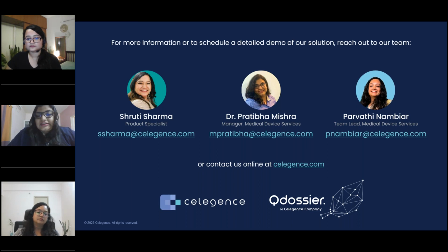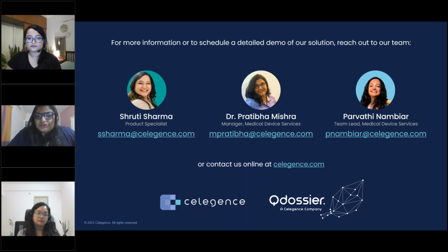In some cases, in case of devices where you don't have necessary data from literature, you can also look into PMS, which basically links to the risk documentation. So what kind of issues or complaints, or adverse events have been reported, and what is the reportable event rate, for example, for similar devices on the vigilance databases, and that can help you define acceptance criteria for safety.